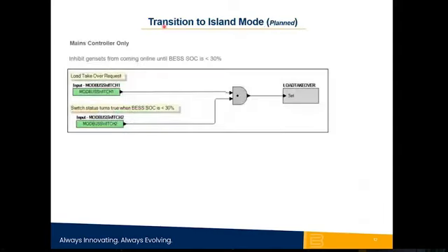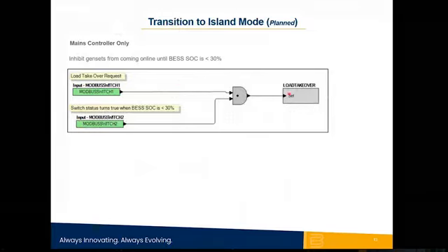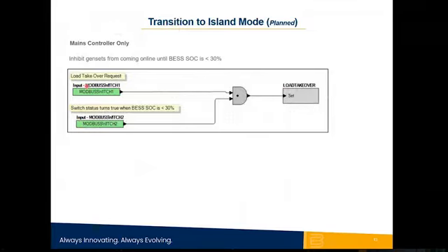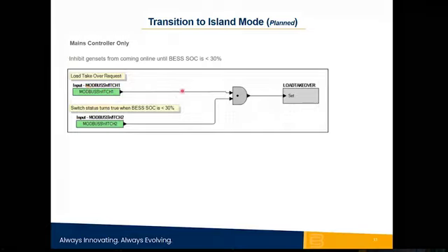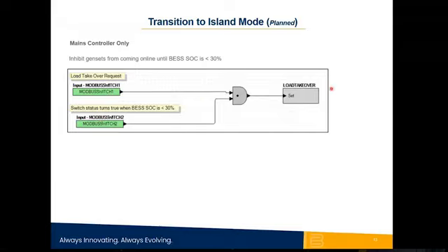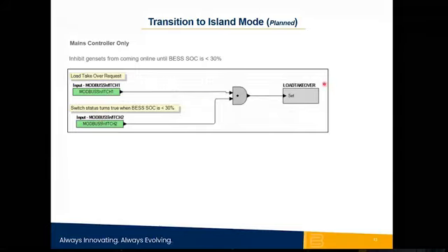If we're transitioning to islanded mode in a planned fashion, then we can use the load takeover logic element. So what we're saying is we're going to send a load takeover request. And then when the state of charge in the batteries is less than 30%, we want load takeover. Load takeover will start the gens. And if it's in close transition, we will parallel the gens to the mains, do a soft load transfer, and then let the generators take over.